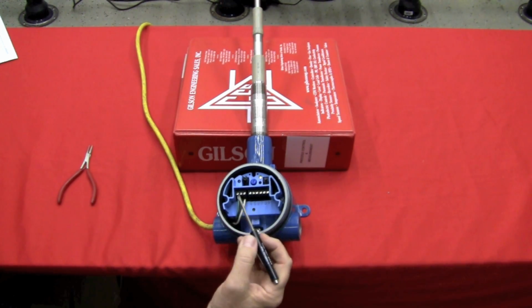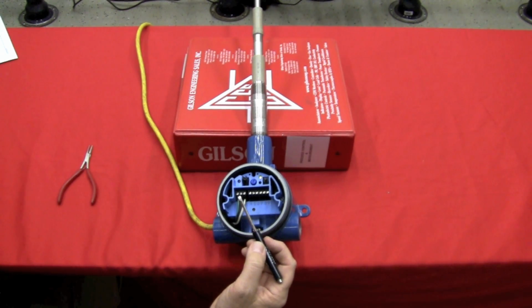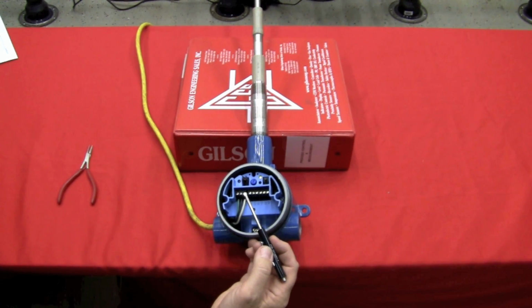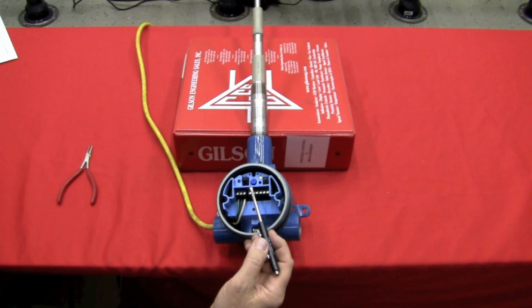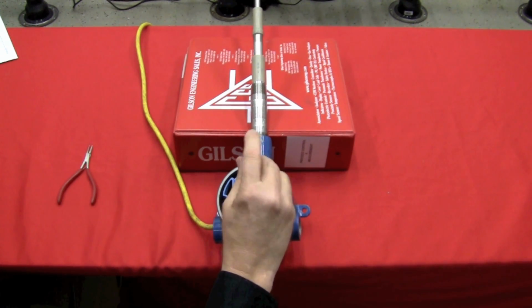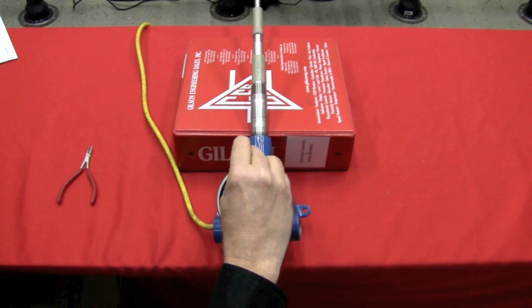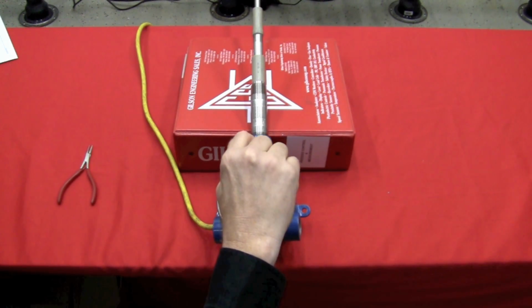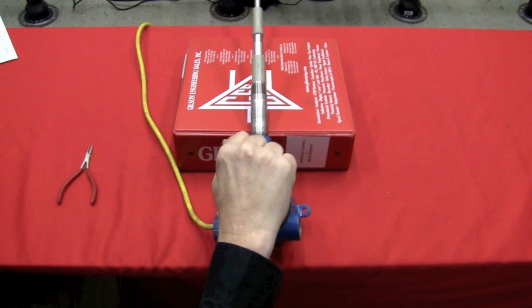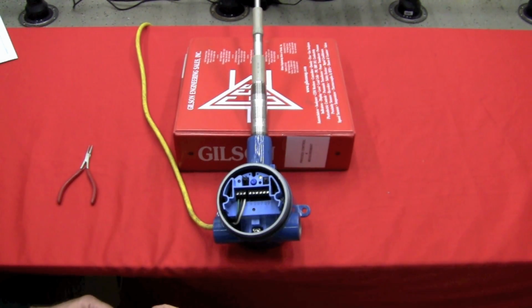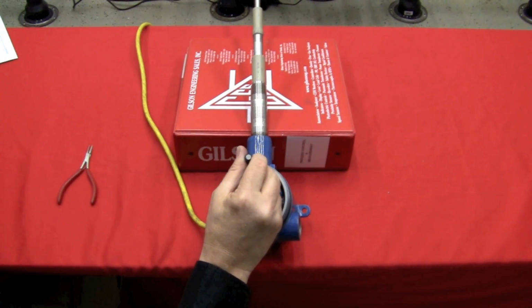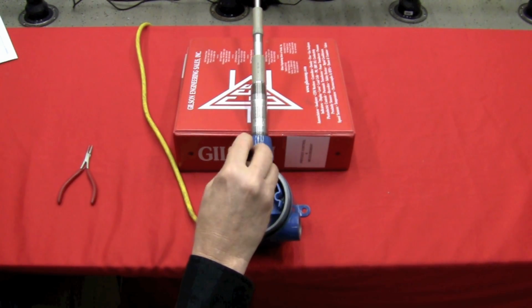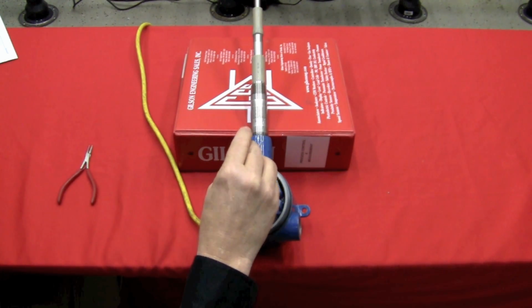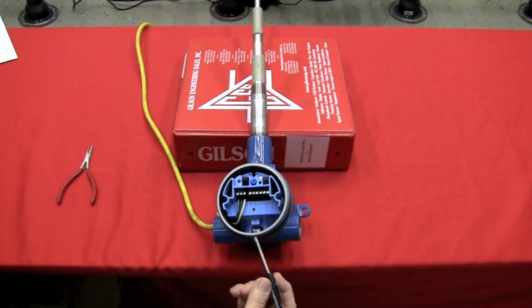The center blue dial is your time delay pot. It's a 270-degree pot, and basically it's from 0 to 60 seconds. So if you take a screwdriver, about 7 o'clock is 0 seconds, and if you turn it all the way around to about 4 o'clock, that's 60 seconds time delay. I'm going to set it back to 0. You want to be careful that you don't overcrank this pot. It's not a full turn pot.